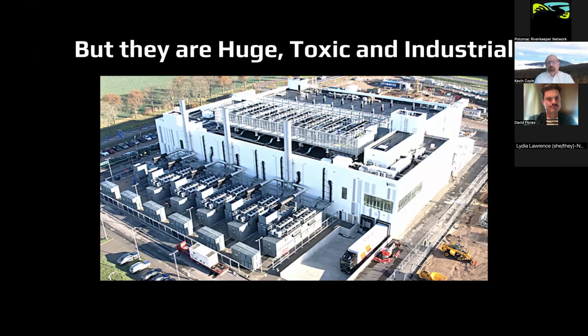The second issue, which gets talked about a lot, is water withdrawals. Some data centers actually rely on water cooling, but most are combined systems. You see in this slide a lot of rooftop blowers, chillers, and so forth — basically air conditioners. They rely on a cooling system that draws water every now and again, and that can add up, because they're building about 1,000 data centers in Northern Virginia and parts of Maryland. So the scale of withdrawal is going to be pretty significant for the Potomac River, even though many of these are closed systems.